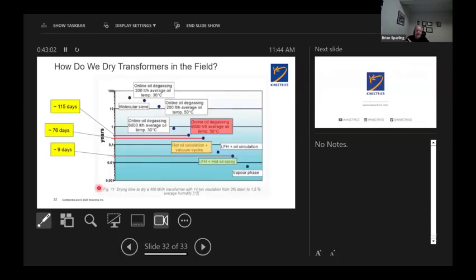That's low frequency heating. And this comes from a paper that was written, a Cigre paper, where somebody had gone away and decided what's the drying time to dry a 400 MVA transformer with 14 tons of solid insulation inside the tank to lower it from 3% down to 1.5% average humidity. So the conventional way, online oil degassing, an average temperature of 50 degrees C, the process I just described before, it's like 115 days. The other one was hot oil circulation and vacuum cycles, 76 days. And somebody has to be there watching this and babysitting it. Low frequency heating and hot oil spray, 9 days.